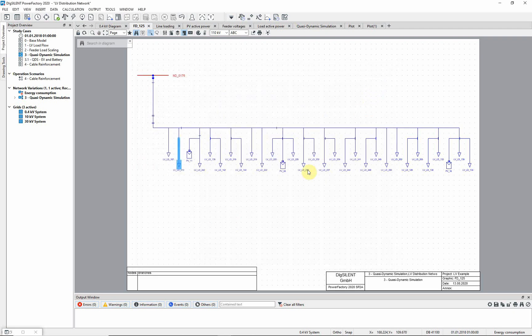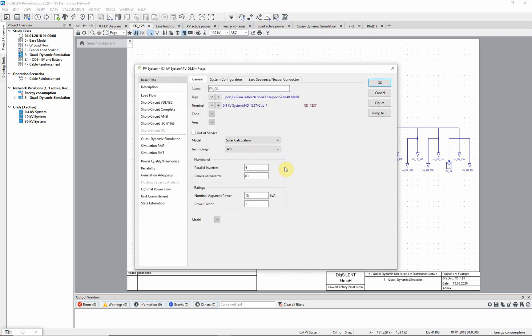Now let's take a closer look at a PV system. Notice that the solar calculation model is used to calculate the in-feed of the PV system. This means that the power in-feed is calculated based on the expected radiation for a particular GPS position, as defined in the busbar to which the PV system is connected.